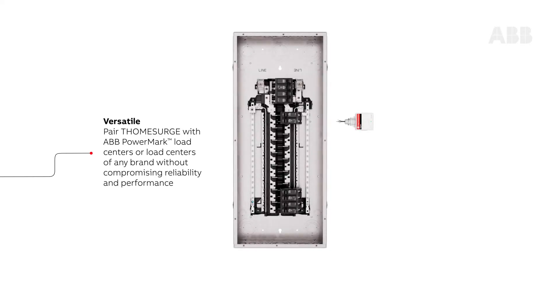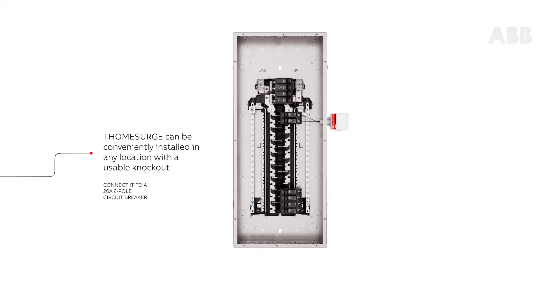Pair THOMESURGE with PowerMark load centers or load centers of any brand without compromising reliability and performance. THOMESURGE can be conveniently installed in any location with a usable knockout, with the optimal position being as close as possible to the main breaker or main lug. Suggested breaker size is a 20-amp two-pole breaker.